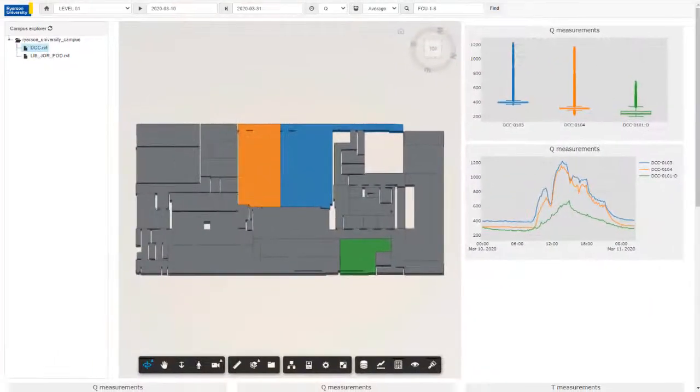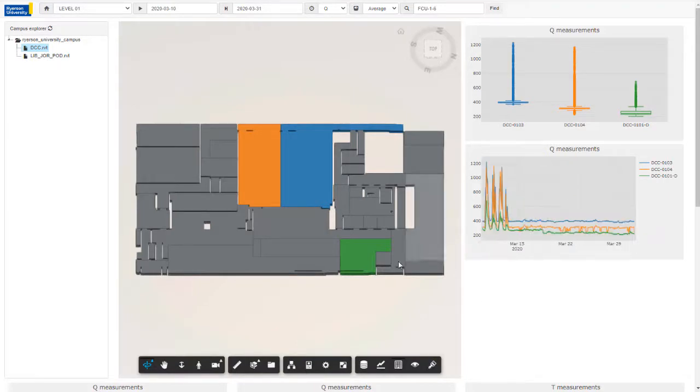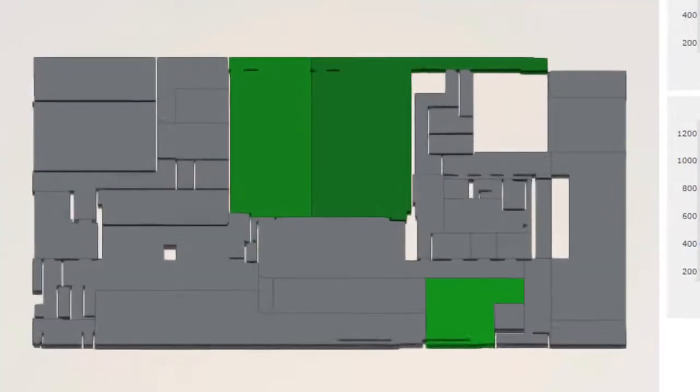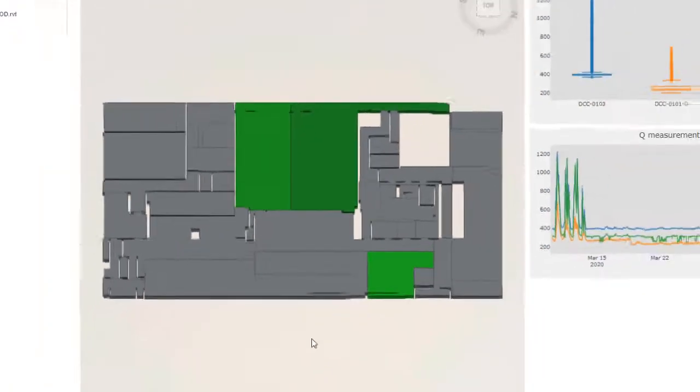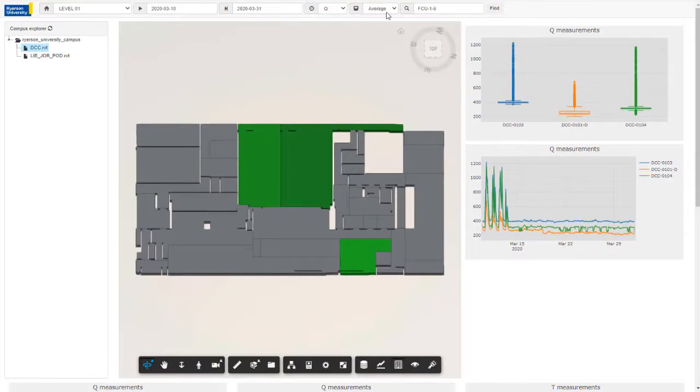The last thing I would like to show in this demo is that it is possible to use another color algorithm to enable comparing rooms visually using a heat map. As we are visualizing CO2 levels, the rooms with lower median CO2 levels are shown with a bright green color, while a darker green indicates a lower air quality due to higher CO2 levels. We can also define which type of aggregation function we want, and if you pick the max, these two rooms are in red as they went at least once beyond the predefined threshold of 800 ppm during this period of time.